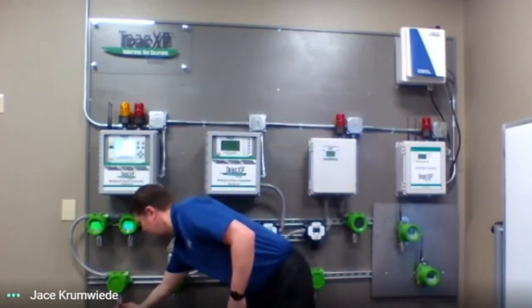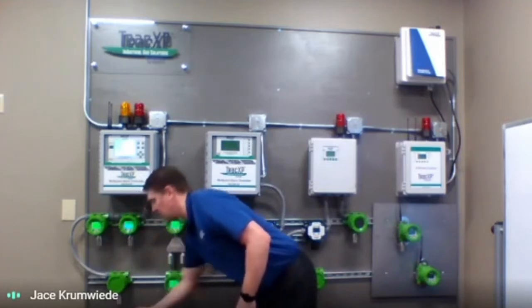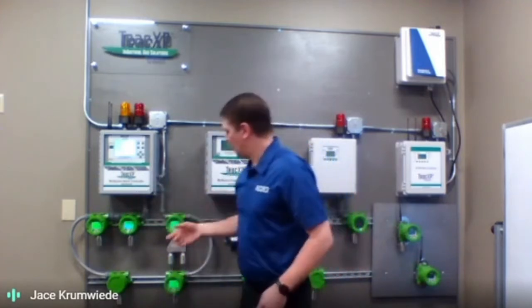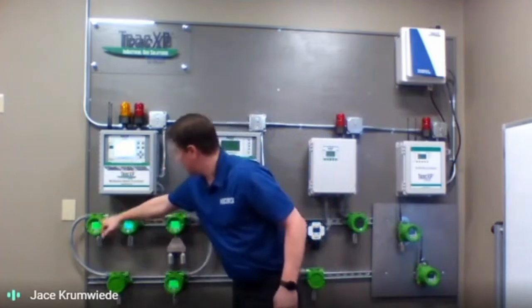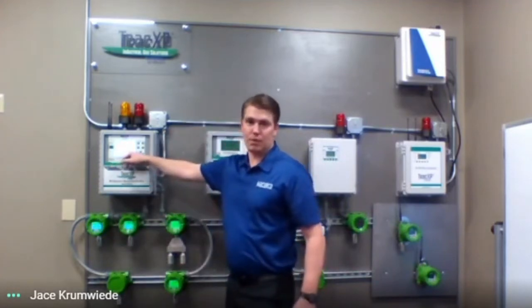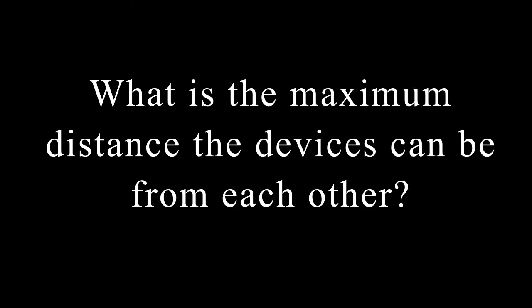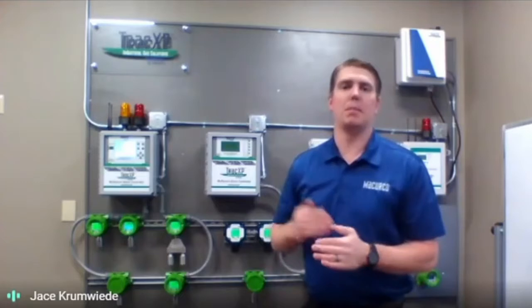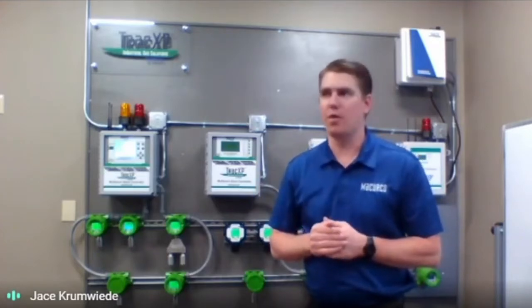You can mount that remotely, and I'll show you using a simple sensor simulator. I'm going to spin that around, and that's going to show you a change in the levels not only at the display, but up here as well. With the T40, it does use Modbus communication to go back and forth, so you're limited by a couple thousand feet. The T30, you are limited up to 50 feet in the right conditions. So if you need to go a lot further, again.